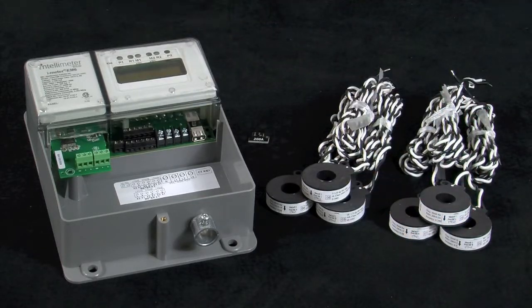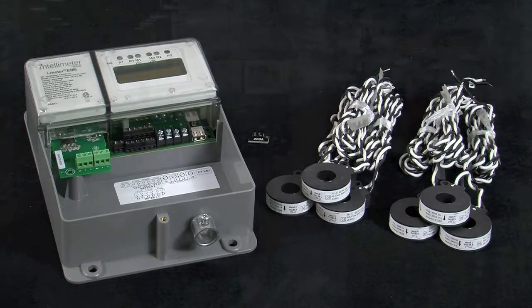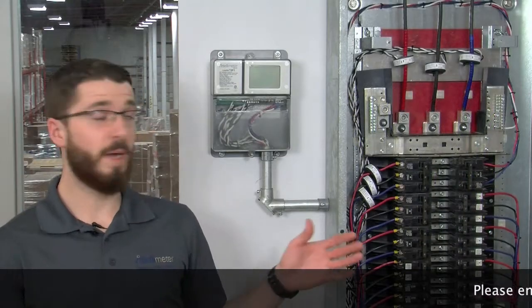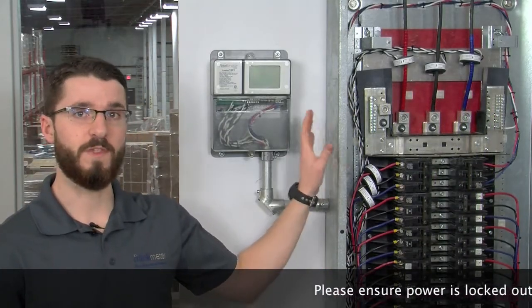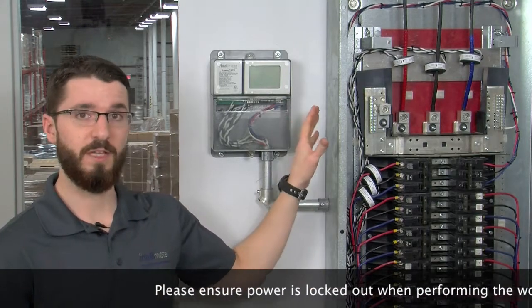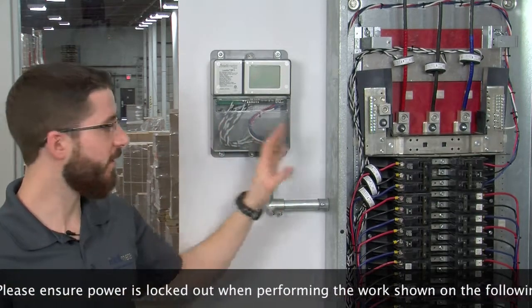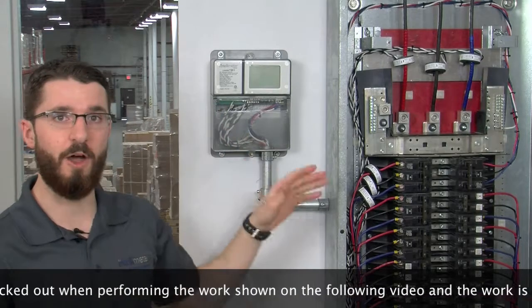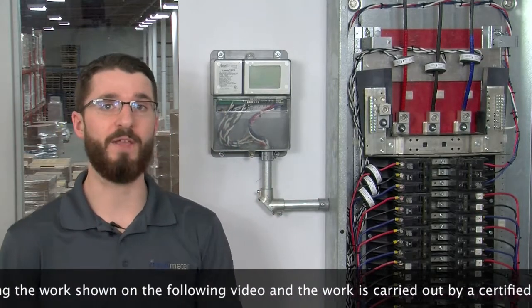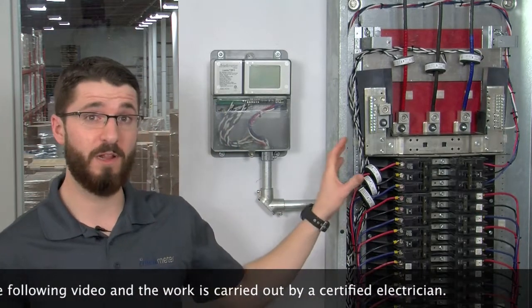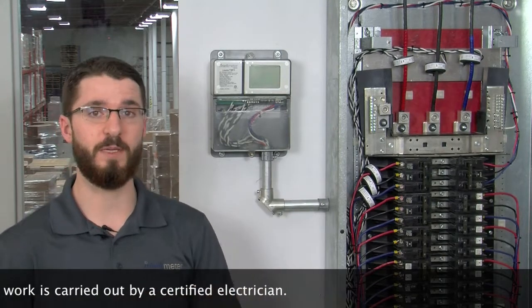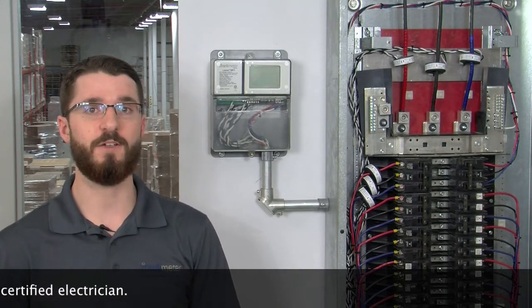So now that we know what each CT is for, let's go ahead and install the CTs. Keep in mind that here we have built a mock-up panel for the sake of this demonstration video. In real-life application, you'd want to ensure that any electrical panels or equipment is totally locked off before opening or performing any work. Now, if work must be performed on the live panel, please ensure that you are wearing the appropriate protective gear, such as an arc flash suit complete with helmet and gloves.